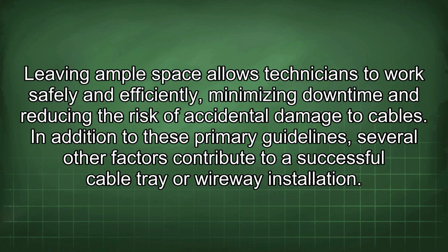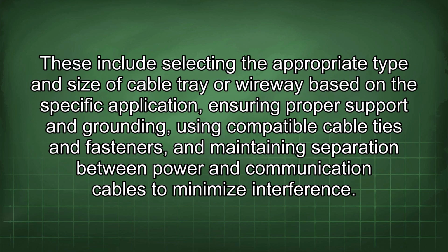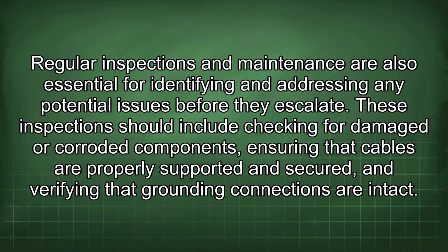In addition to these primary guidelines, several other factors contribute to a successful cable tray or wireway installation. These include selecting the appropriate type and size of cable tray or wireway based on the specific application, ensuring proper support and grounding, using compatible cable ties and fasteners, and maintaining separation between power and communication cables to minimize interference. Regular inspections and maintenance are also essential for identifying and addressing any potential issues before they escalate. These inspections should include checking for damaged or corroded components, ensuring that cables are properly supported and secured, and verifying that grounding connections are intact.